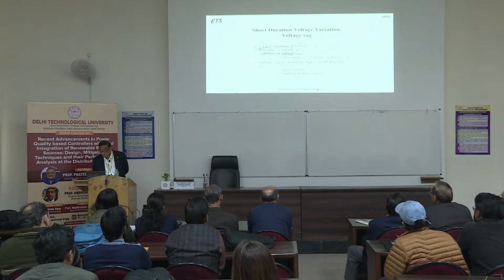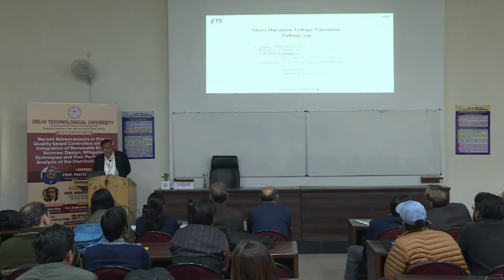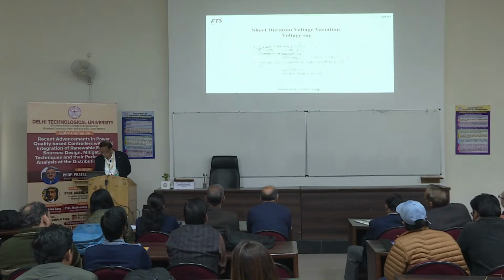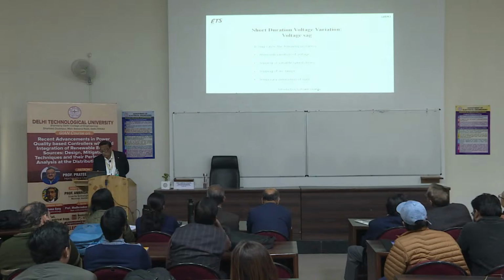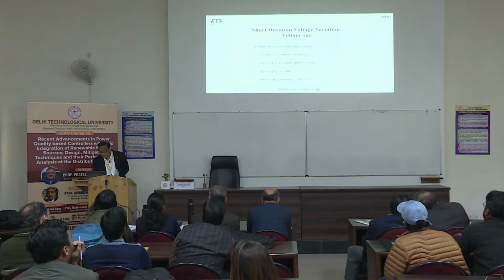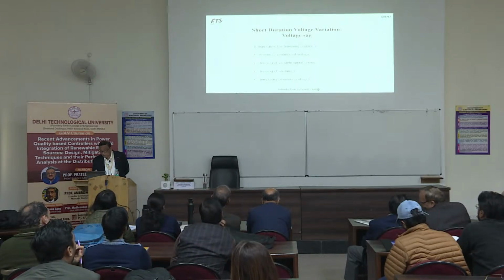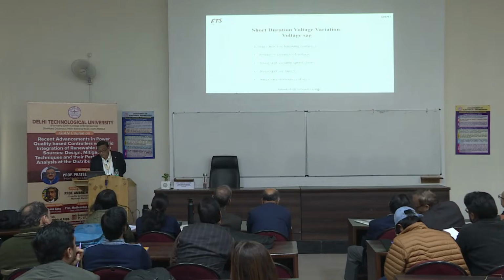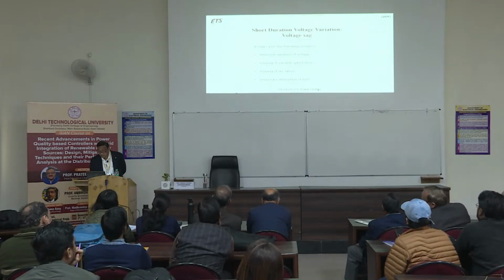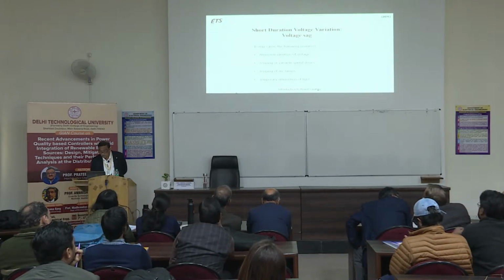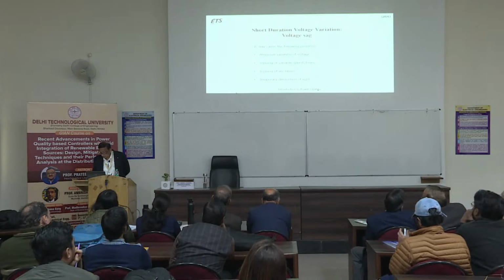Voltage sag is caused by high current flow due to system faults, starting of large motors, as we have already discussed. Short duration voltage sag may cause the following problems: abnormal variation of voltage, tripping of variable speed drive, tripping of arc lamps, temporary diminution of light.